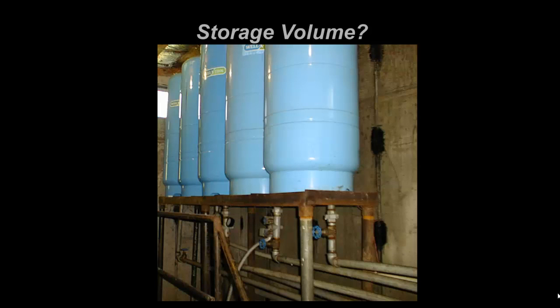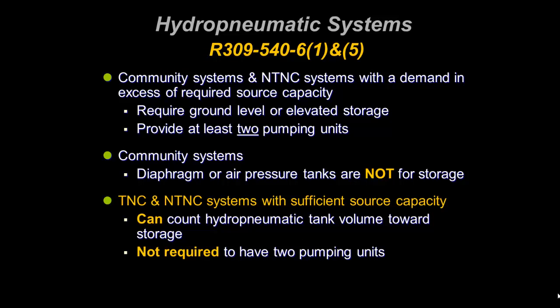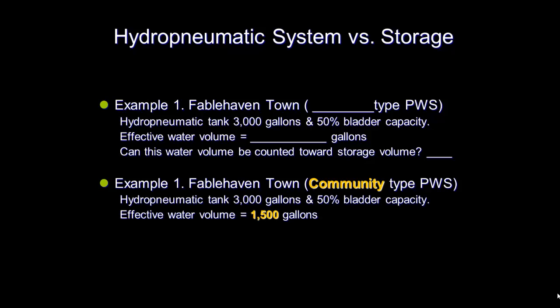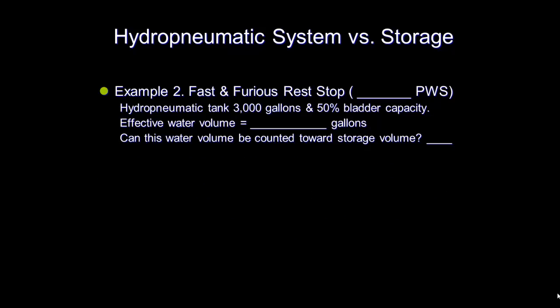We get many questions regarding the storage volume of hydropneumatic tanks. Can the volume of these tanks be included towards the required storage capacity? The answer is: it depends. Community and non-transient non-community systems with demand in excess of their source capacity require gravity storage tanks and must provide at least two pumping units. So for community drinking water systems, hydropneumatic tanks cannot be counted towards the required storage volume. To help explain this, the following scenario is given for the fictitious Fable Haven Town. This system has a hydropneumatic tank with a volume of 3,000 gallons with a 50% bladder capacity. Since this is a community water system, the effective volume of 1,500 gallons cannot be counted towards the needed storage capacity.